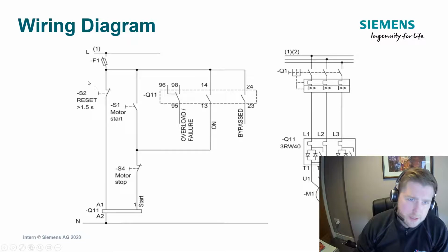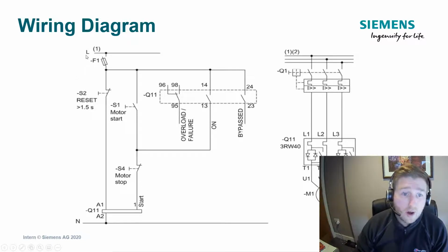So in this control circuit, similar to the 3RW30, you have your IN signal, which is going to terminal 1. So terminal 1 is for IN. On that signal you'll have a start and a stop command for the motor, and on A1 and A2 you also need to initiate the control voltage to ensure that the device starts. A1 and A2 have to be in use, and also the signal to terminal 1 has to be engaged for the motor to actually initiate a start.